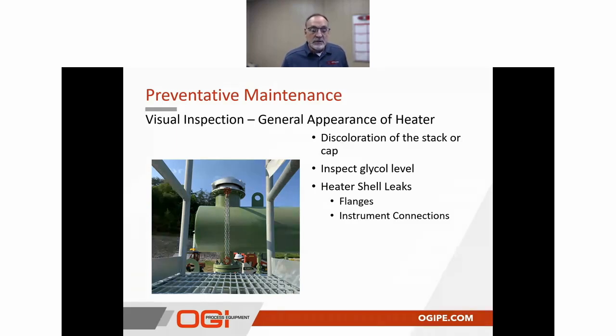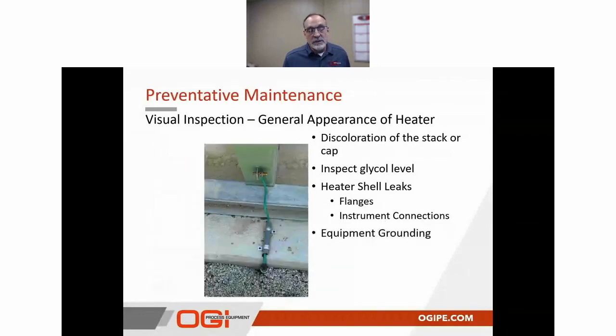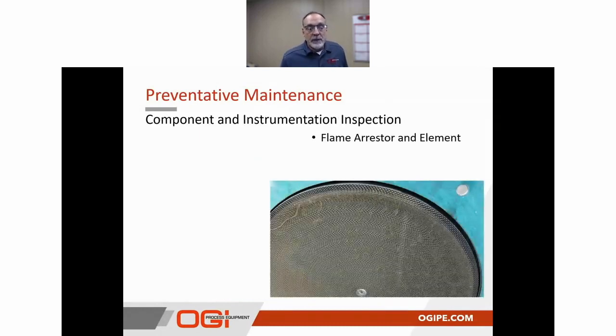As far as the heater shell leaks, we're going to look at the shell flanges. We're going to look at instrument connections that are in the shell, and the next step is the grounding. Is the heater properly grounded, and are those connections still valid? After we've gone through a general visual walkthrough, we're going to take a more concentrated look at the components and instrumentation associated with the heater.